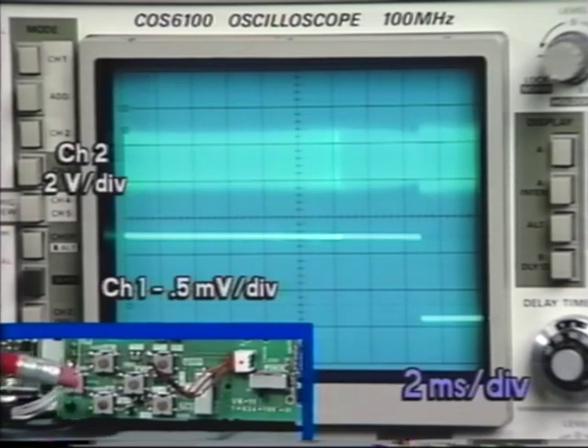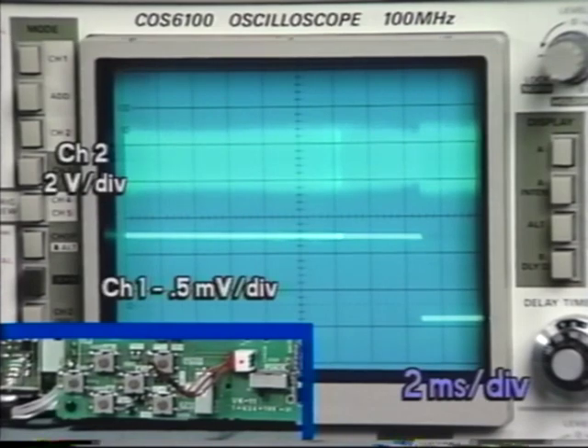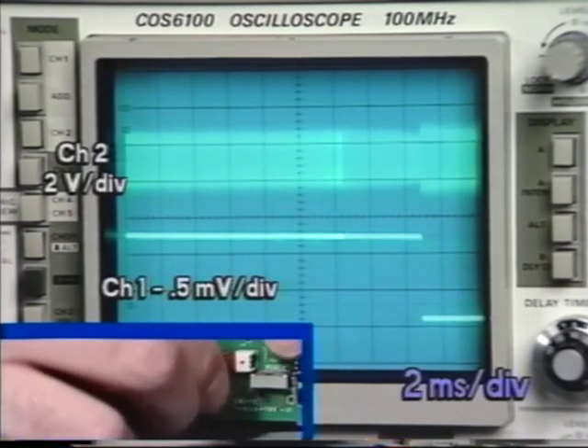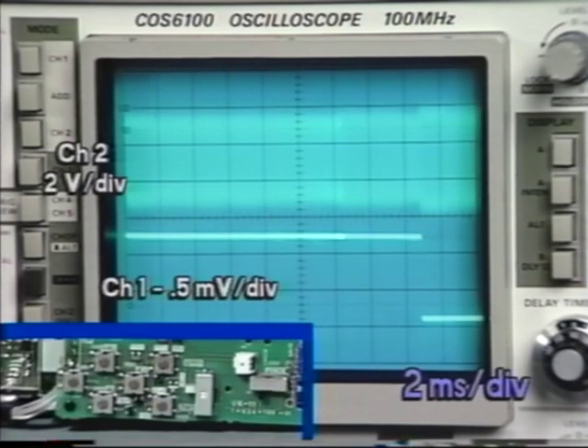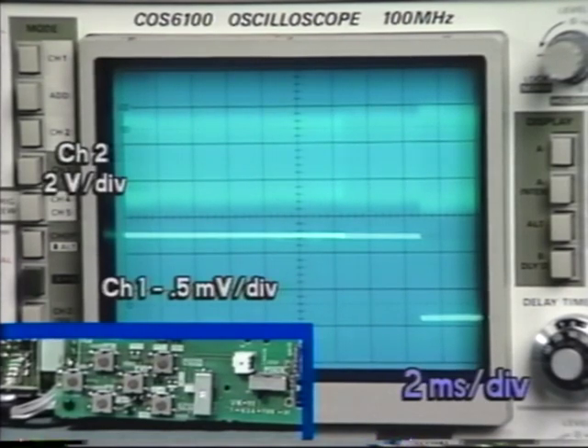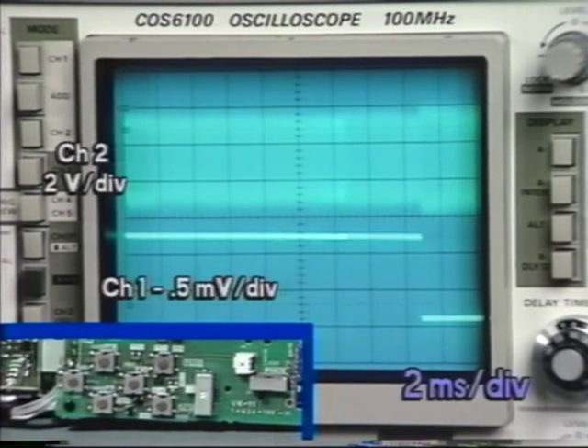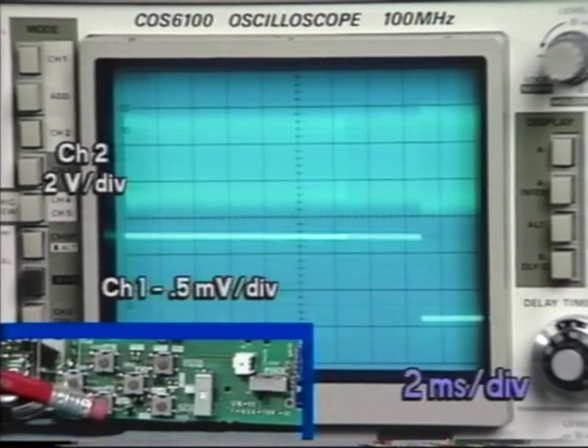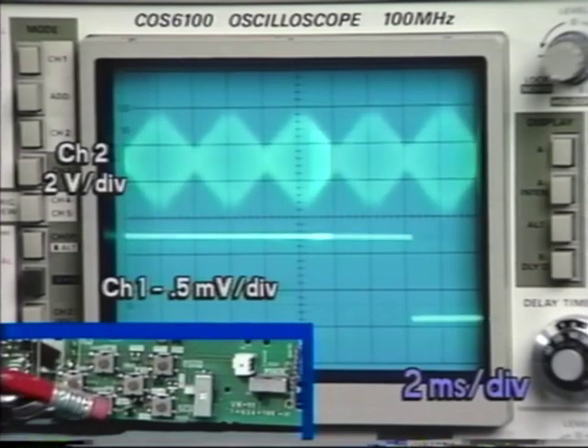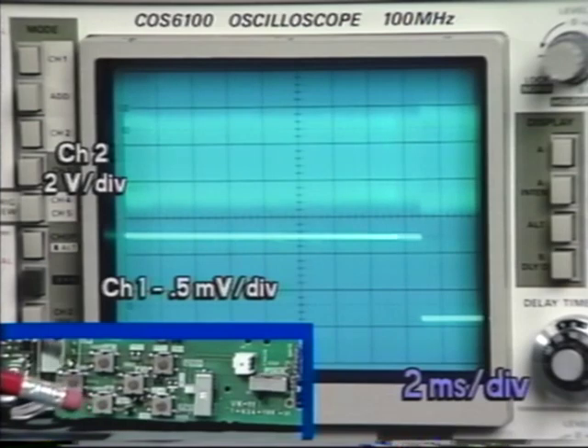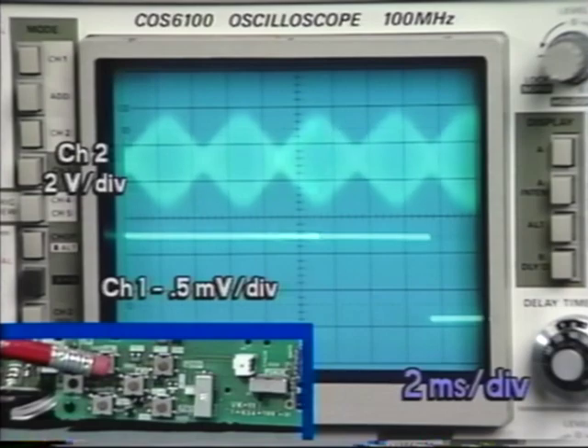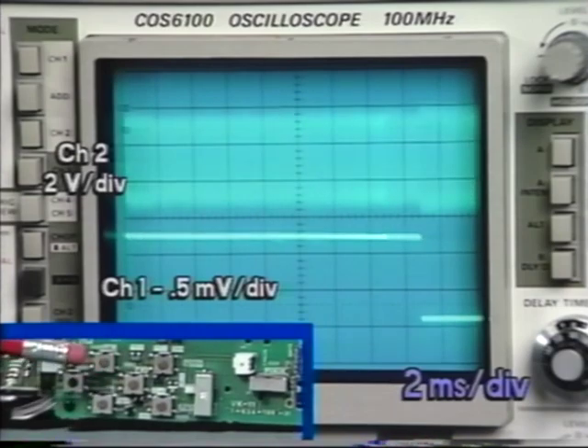As a final check, remove the 3-pin connector from CN508 on the VK1 board. The RF envelope should return to its normal amplitude and it should also be flat. Finally, recheck the RF envelope signal in the cue and review mode. If the peaks maintain a constant pitch and the RF envelope returns to its normal amplitude within 2 seconds of releasing cue or review, tape path has been properly adjusted.